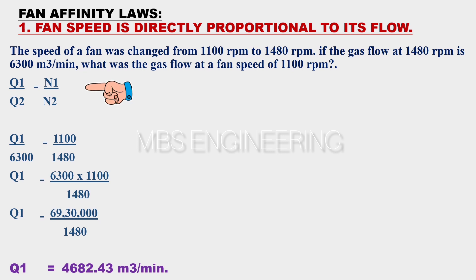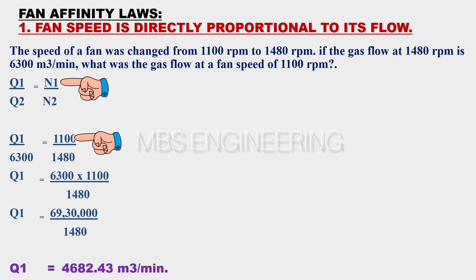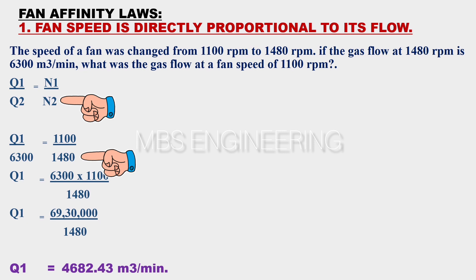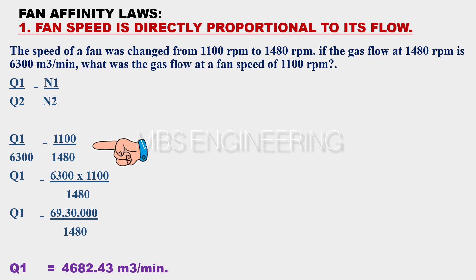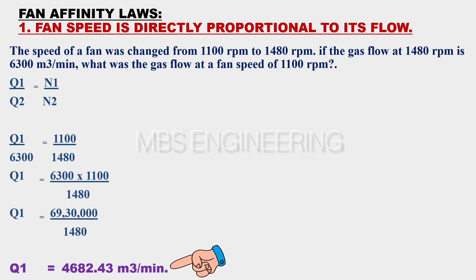Where Q1 and Q2 are flow in cubic meters per minute. The given data are: flow Q2 is 6300 cubic meters per minute, speed N1 is 1100 RPM, and speed N2 is 1480 RPM. We need to calculate Q1. Q1 divided by 6300 equals 1100 divided by 1480. Please refer to the below step-by-step calculations. The obtained flow Q1 is equal to 4682.43 cubic meters per minute.